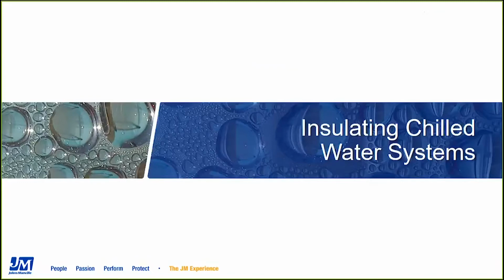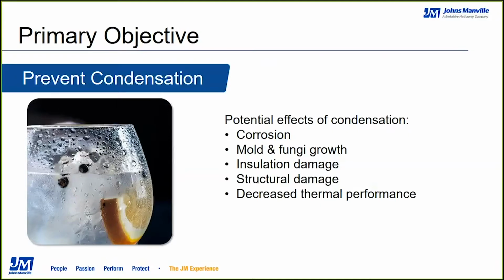Okay, so insulating chilled water systems is a special insulation system that has special considerations and special needs during installation. So we're going to talk about that here. And really the primary consideration is that the system is designed and installed to prevent condensation. The risks around allowing condensation to occur are that you could get corrosion of the pipe or equipment that you've insulated. Moisture is needed for mold and fungus growth. So you are definitely looking to prevent condensation to avoid those two potentials.